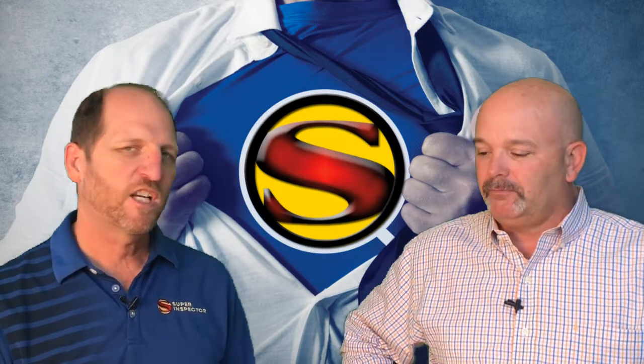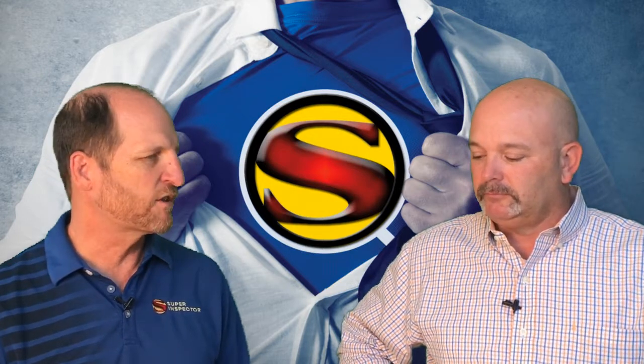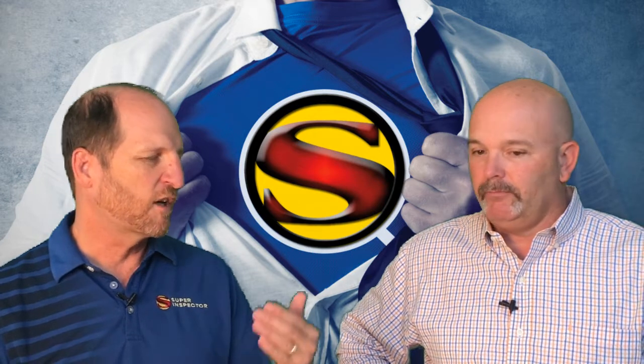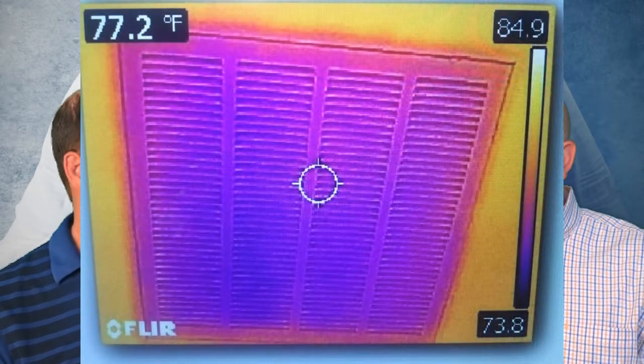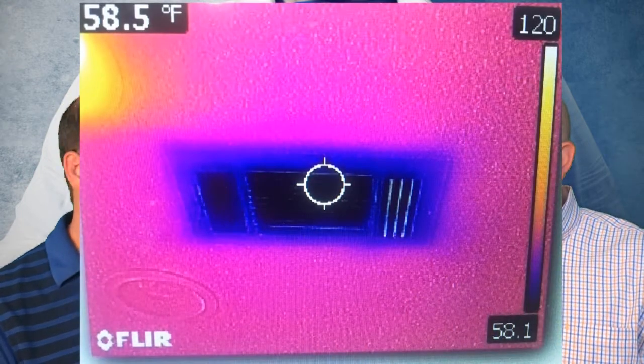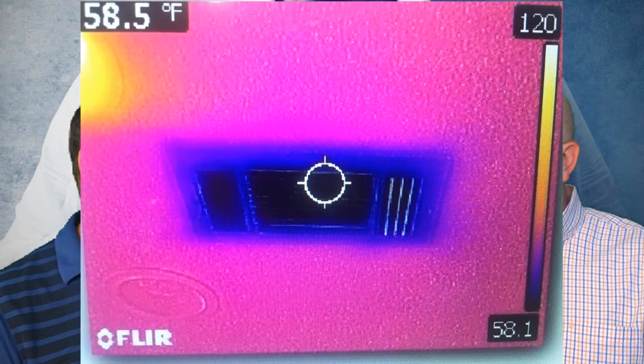And then, of course, we check temperature differentials to see that the temperature of the return air and the supply air, we like for the difference between those two to be 15 to 22 degrees. Right. If it's outside of that range, that indicates that the system's not cooling like it should.